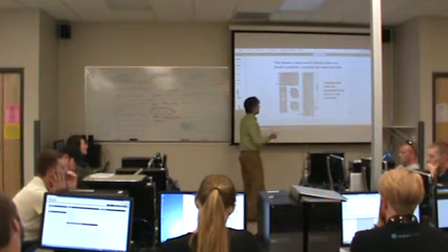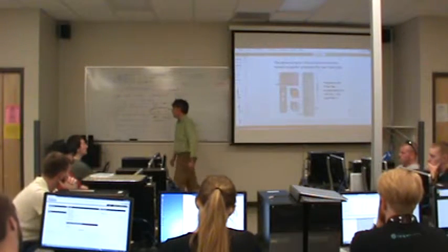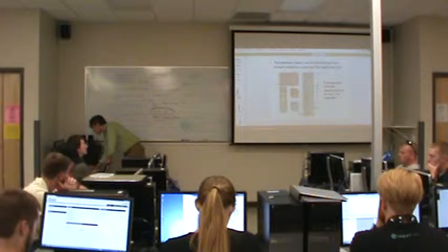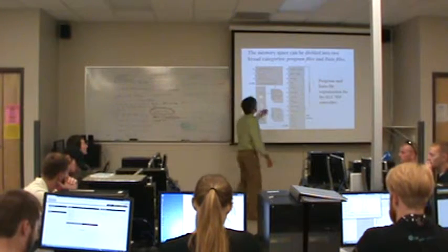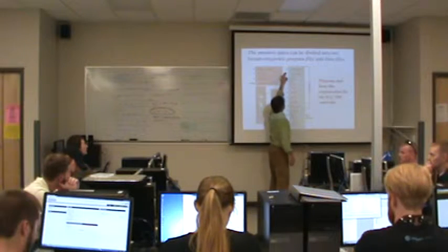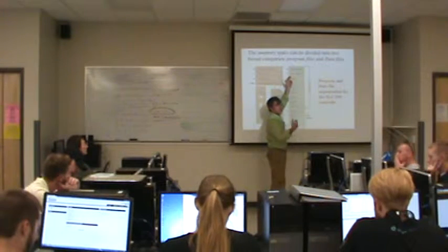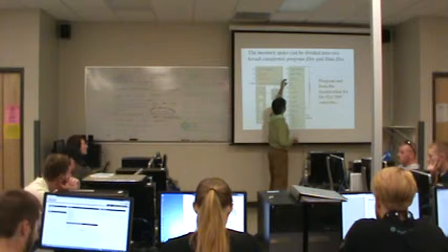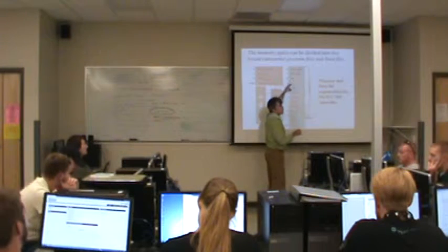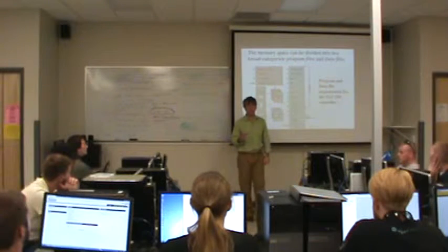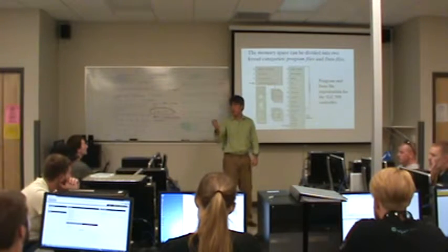But just for information, I've mentioned this a little bit, but the memory in Allen Bradley PLCs at least is typically organized this way. It's organized into files, so file 0 is associated with the outputs, file 1 is associated with inputs, file 2 is the status file, then you've got the bits file. And remember, the bits file is the file I showed you last time, where you can store information.